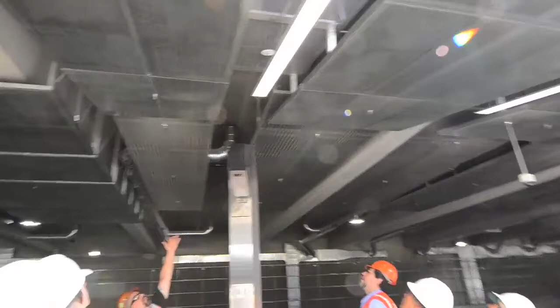If you look through the ceiling, you'll see that rectangular box, that's the driver for the fixture. You don't have any high voltage power in that light. The power goes into the driver, 277 volts, and then out of the driver to the light fixture through the little gray cable. So if you need to get up there, we located everything right there at the end so you can get to it with your hands without taking the ceiling apart.